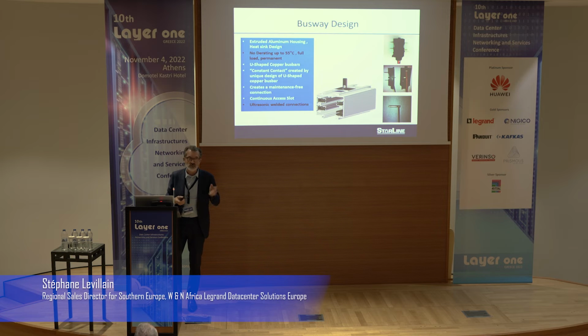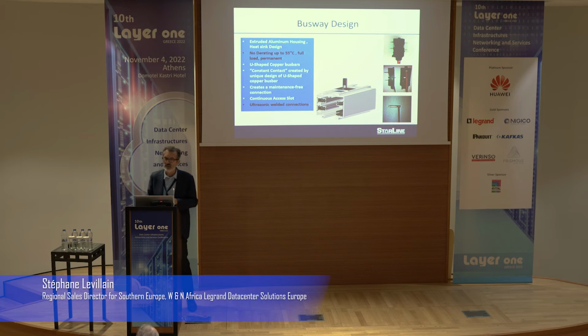That means that with the Starline busway solution, you have no derating, absolutely no derating, up to 55 degrees Celsius, full load, permanent. So you could install the Starline busway system in a cold air or a hot air containment. It doesn't matter, which is not the case for some other solutions you can find on the market.